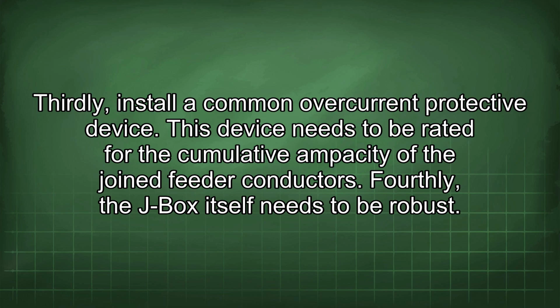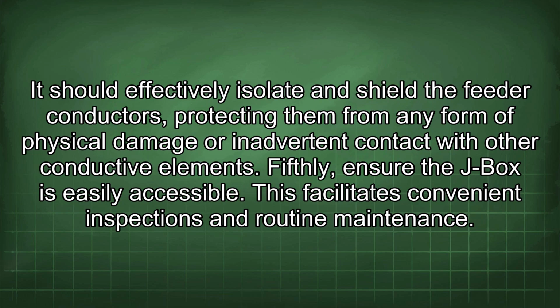Thirdly, install a common overcurrent protective device. This device needs to be rated for the cumulative ampacity of the joined feeder conductors. Fourthly, the J-box itself needs to be robust. It should effectively isolate and shield the feeder conductors, protecting them from any form of physical damage or inadvertent contact with other conductive elements. Fifthly, ensure the J-box is easily accessible. This facilitates convenient inspections and routine maintenance.